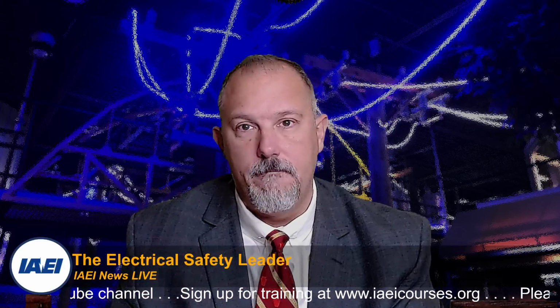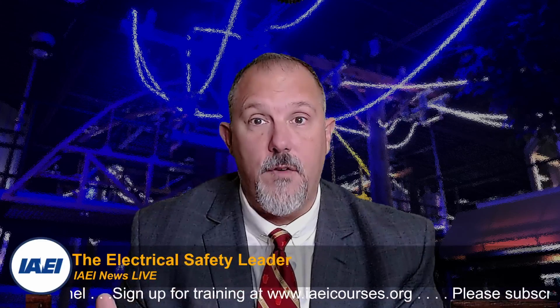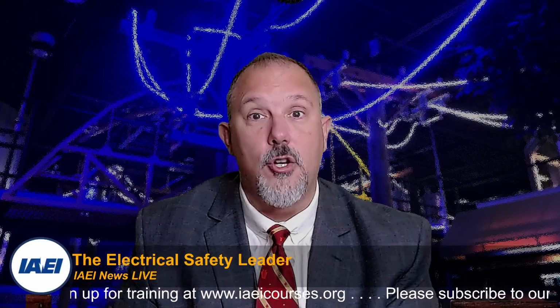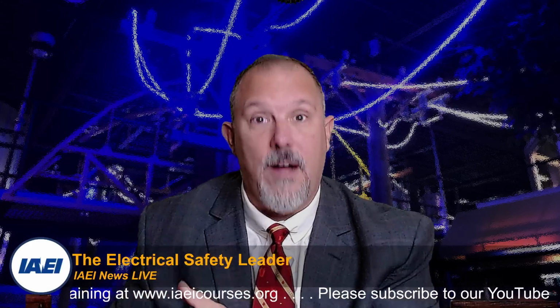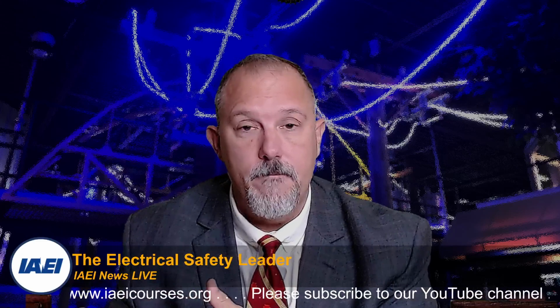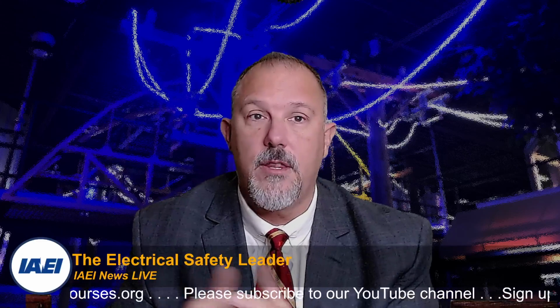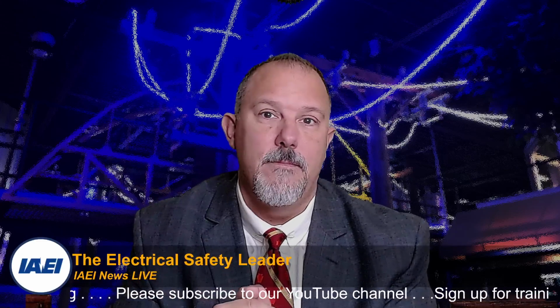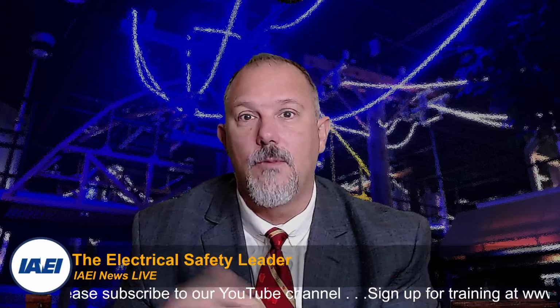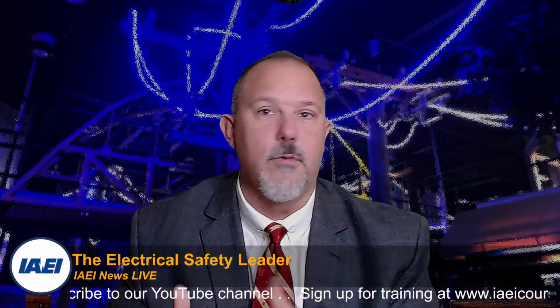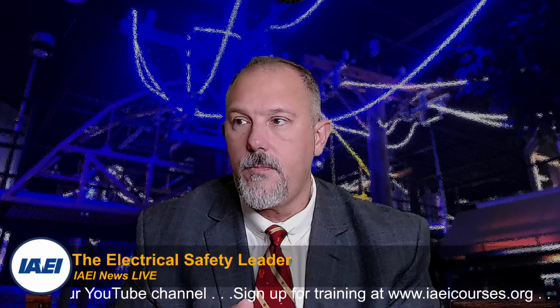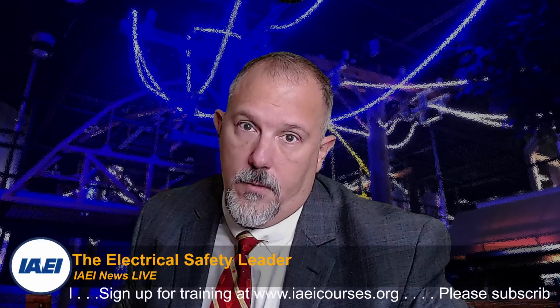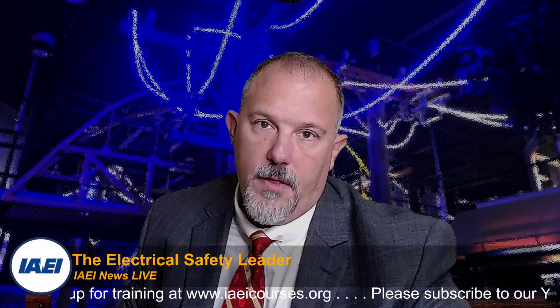The moment that current goes outside of the normal path, that is when I have a short circuit. I could have a ground fault. If it goes outside of the path and goes to ground, that's a ground fault. That's a short circuit current. I could have a short circuit that goes from line to neutral, line to ground. All of those are fault currents. So now, an overload, think about an overload. Think about what's going on.